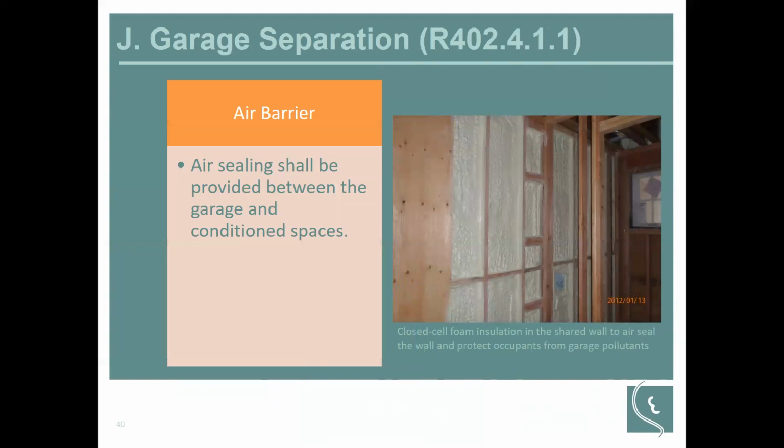For garages, making sure that we air seal between the garage and the living space. As noted here in this picture, we are trying to protect the occupants in the home from the pollutants that may be in the garage, and making sure that the pollutants don't enter the home. This is also a good reason why you should not want to put a furnace or air handler in the garage, because you don't want any of that air and the pollutants from the air entering that air handler and then being distributed into the house. And this is also crucial that this air sealing be complete.